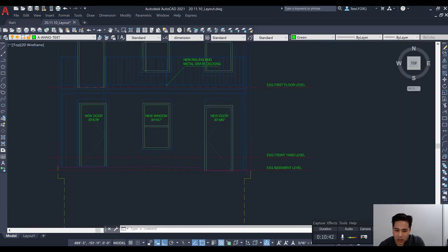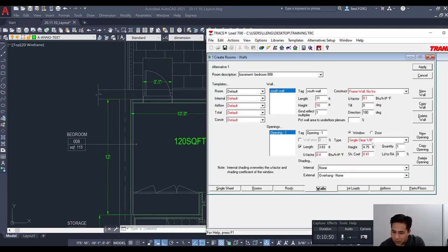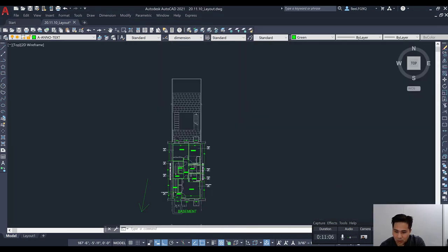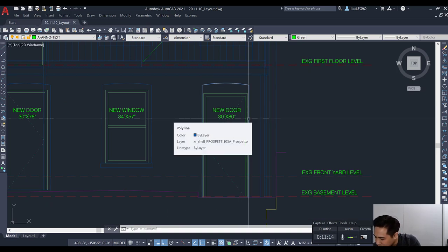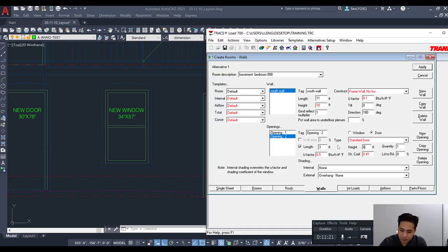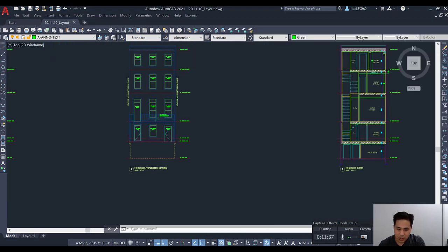We also need to input the door opening. Click 'new opening' and select door. The door length is 3 feet 1 inch — we'll simplify to 3 feet. The height from the elevation is 80 inches, and 80 ÷ 12 = 6.67 feet. Quantity is one. The red values for U-factor are from the template we set up. That covers the south wall.